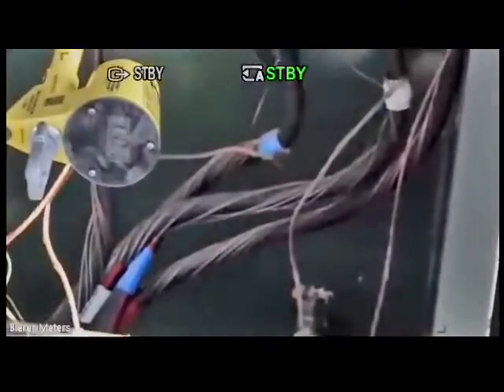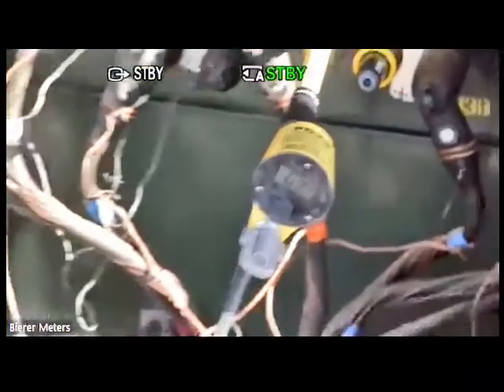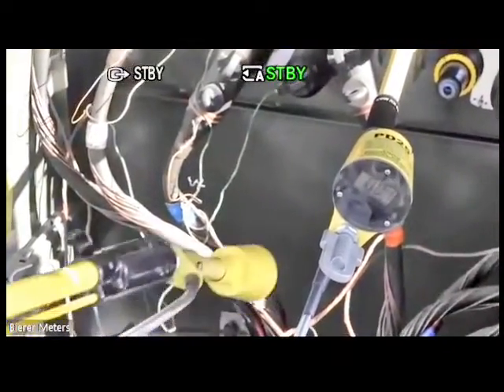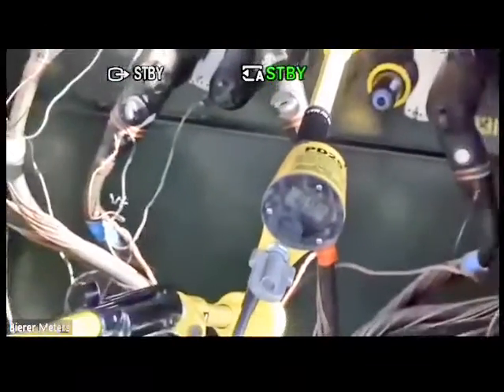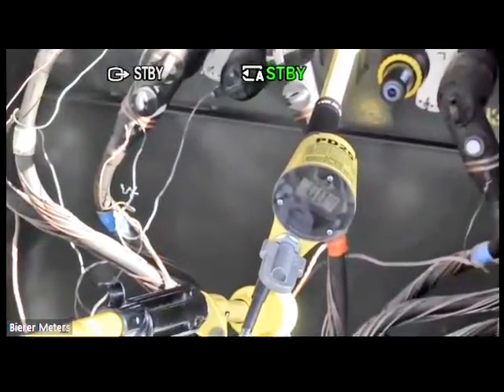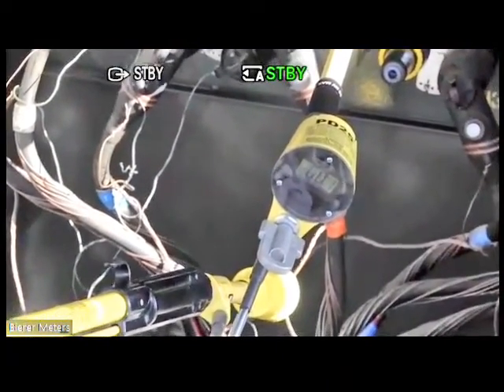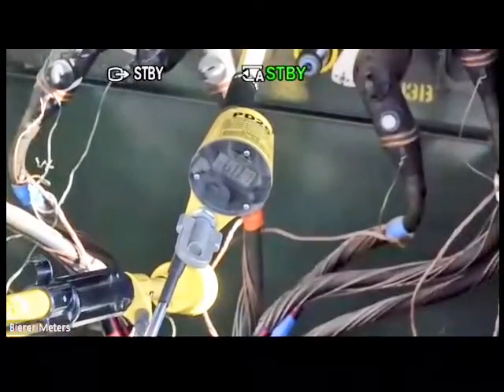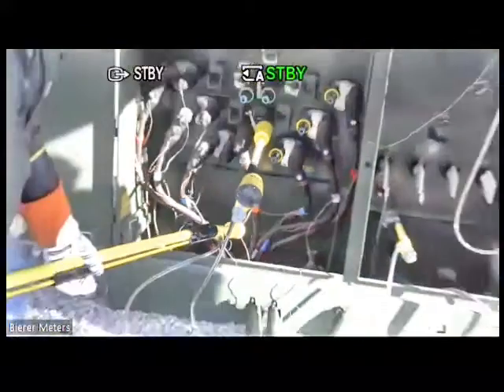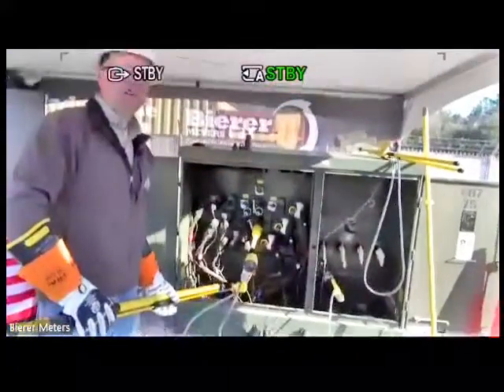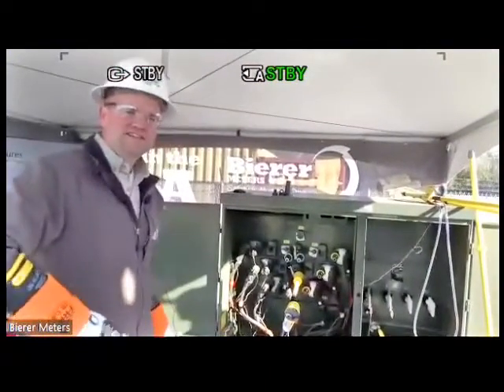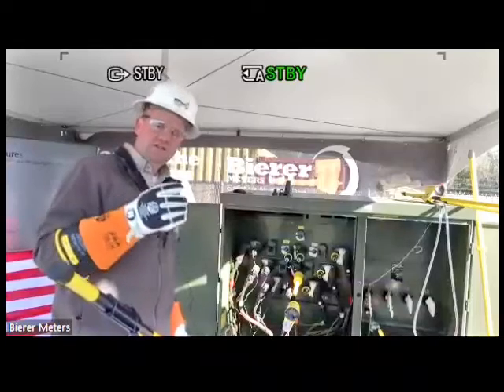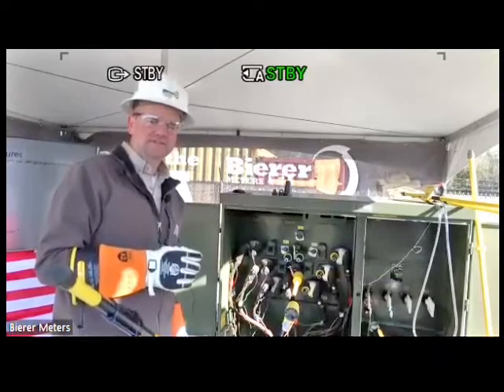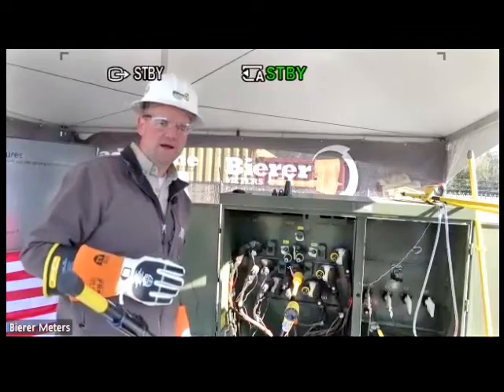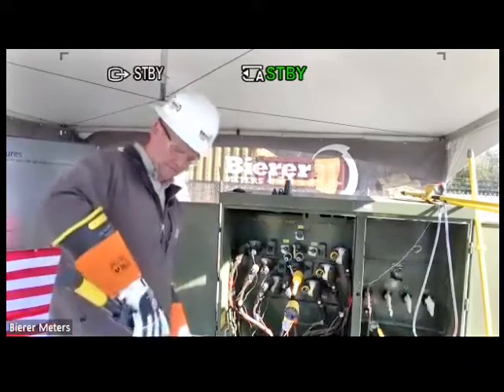And my second probe, I want to take it to ground. So watch whenever I touch ground with this, watch that number. You should see it spike and then go down. So it went almost to 1 kV and then went down to nothing. Okay. So again, with the accuracy built into the tool, you can see exactly how much potential is on it once you de-energize it. So you know you fully de-energize that primary cable. Now it's safe to handle.